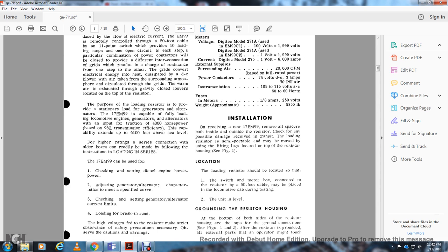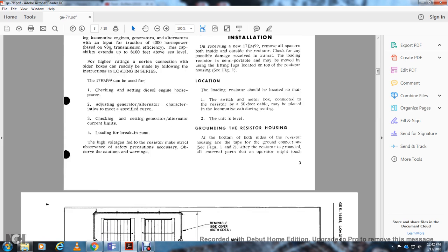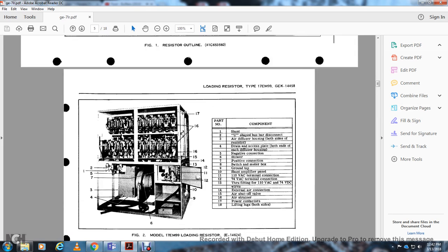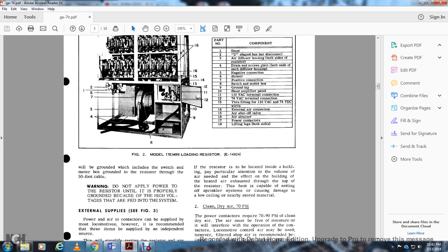The unit should be level. Ground the resistor and housing. At the bottom of both sides of the resistor housing are the tapped holes for the ground connection, see figures 1 and 2. After the resistor is grounded, all external parts that the operator might touch will be grounded, to include the switch and meter box, grounded to the resistor through the 50-foot cable. Warning: do not apply power to the resistor until it is properly grounded because of the high voltage fed into the system.